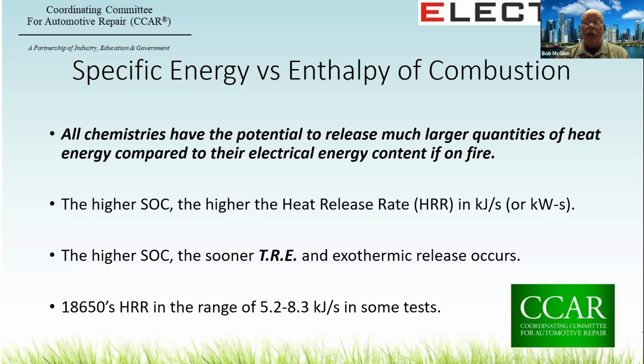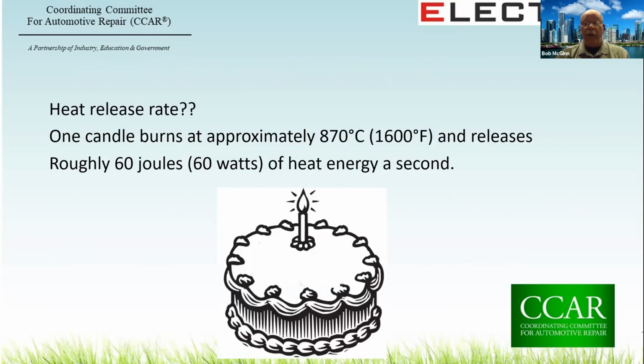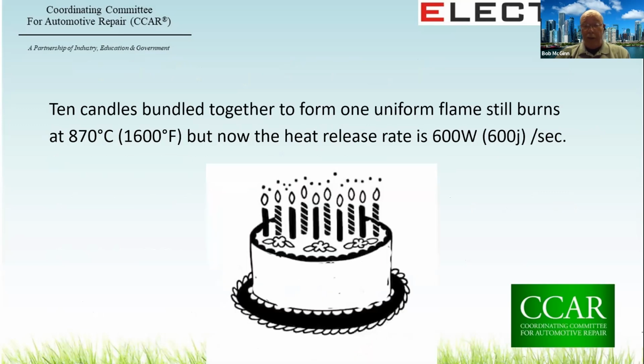The higher the state of charge, the sooner thermal runaway and exothermic release will occur. I threw in a new term, heat release rate, just so everyone's clear. We use the birthday candle example: one candle will burn at approximately 1600 degrees F and has a heat release rate of about 60 watts a second. And who knew that joules and watts were the same? 10 candles will still burn at about 1600 degrees, but now the heat release rate is 600 watts a second.